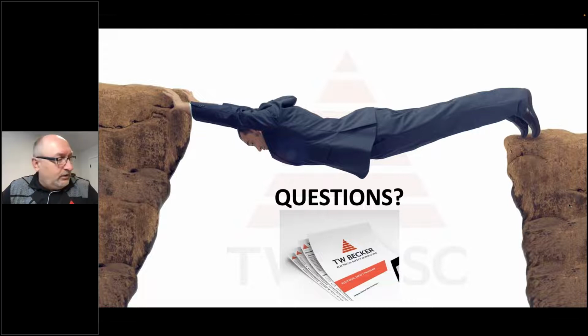Dr. Ralph Lee, right, his original research which is documented in the IEEE Yellow Book, now the 3007 series, way back then, his graph was included. And it says that blast pressure correlates to abnormal arcing fault. It has nothing to do with incident energy. So 40 calories per centimeter squared was miscommunicated in 70E and Z462 because there was a little note that said at greater than 40 calories, greater emphasis is required. That was a tech committee error as well, but they voted on it based on the information they had at the time, and it was removed when additional information was presented that said, hey, that was wrong, right?